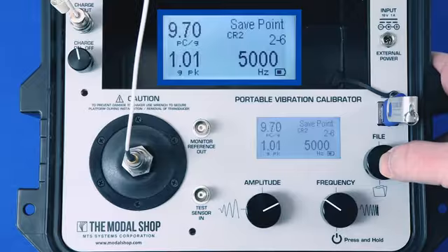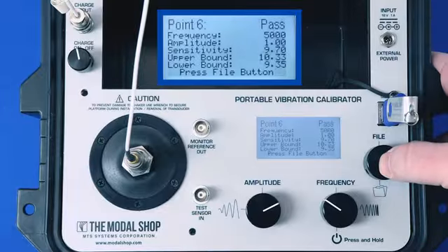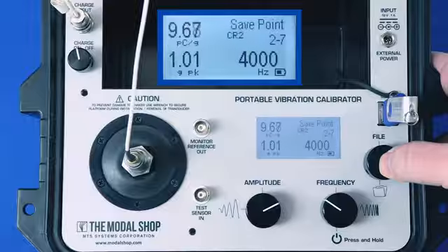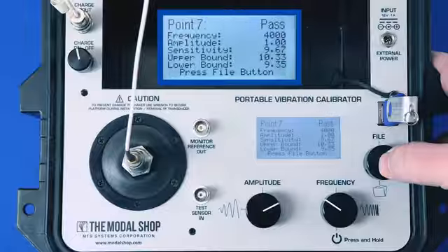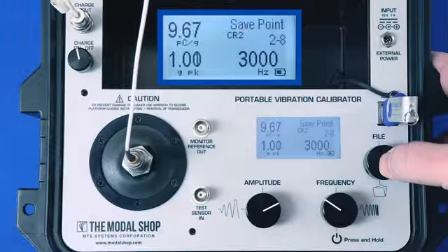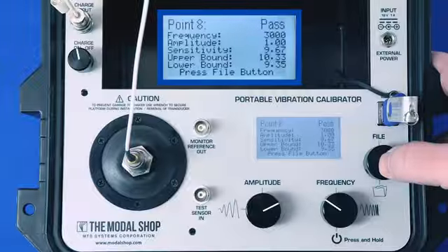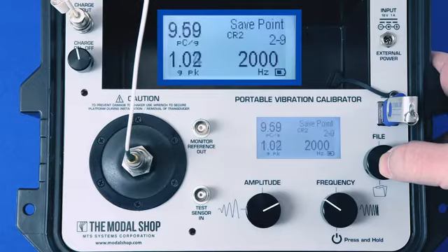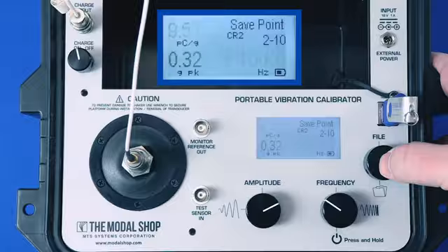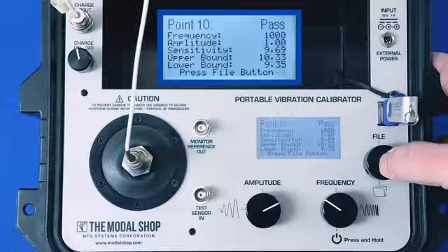So I'm going down in a frequency sweep down in the thousands here, and we're going to stop at 10 Hertz. So I have quite a few more points to go. The amplitude on the screen is the actual vibration amplitude as measured by the reference accelerometer that's in the shaker. So you want to wait for that number to settle on 1 G peak or whatever you programmed, and then just make sure the sensitivity also settles. And this transducer has a lot of stability, so it doesn't take very much time to settle. A couple seconds at each test point is all it takes.